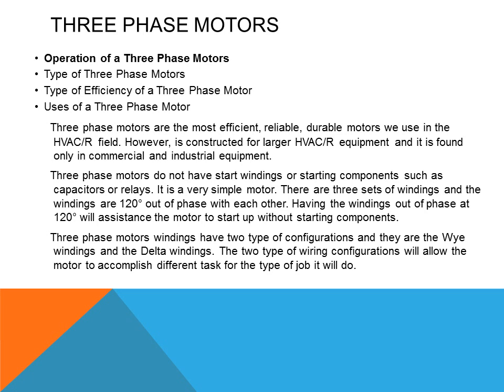Three-phase motors are the most efficient, reliable, durable motors we use in the HVAC field. However, they are constructed for larger HVAC equipment and are found only in commercial and industrial equipment. Three-phase motors do not have start windings or starting components such as capacitors or relays — it is a very simple motor. There are three sets of windings and the windings are 120 degrees out of phase with each other, which assists the motor to start up without starting components. The three-phase motor windings have two types of configurations: the Y winding and the delta winding, which allow the motor to accomplish different tasks for the type of job it will do.